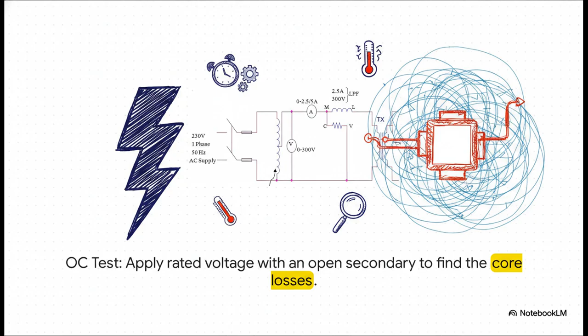So how do you measure that idling loss? Well, in the open circuit test, we apply the normal rated voltage to the input side, but, and this is the key, we leave the output side completely disconnected. With no load attached, the tiny bit of power the transformer draws is exactly equal to those core losses. It's simple, but really effective.